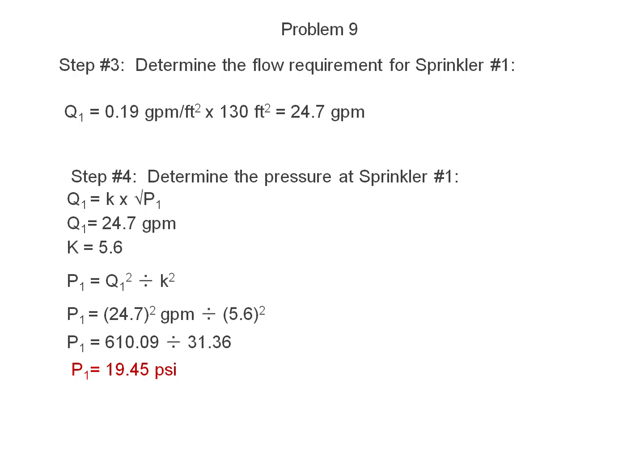Problem 9, determine the flow requirement for sprinkler number 1. The flow, or Q1, is equal to 0.19 gallons per minute per square foot times 130 square feet per sprinkler, which will equal 24.7 gallons per minute.